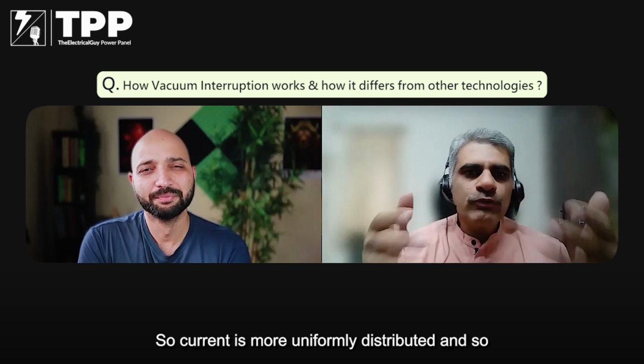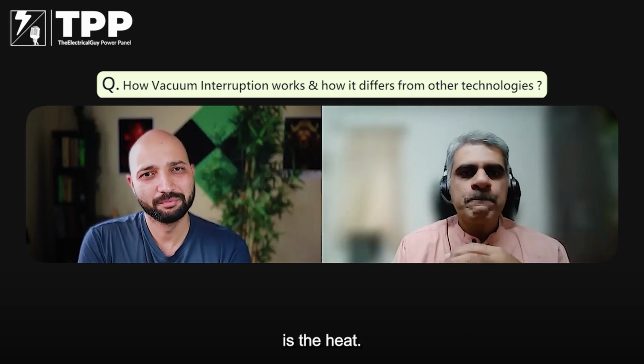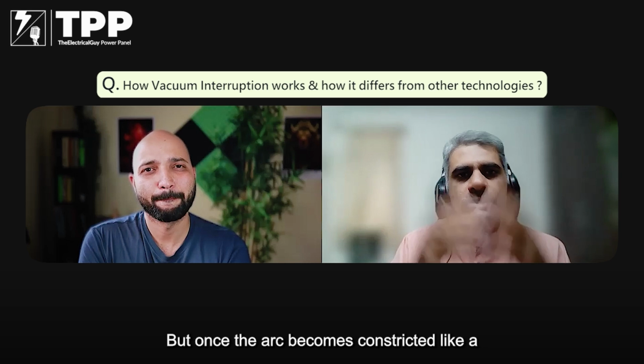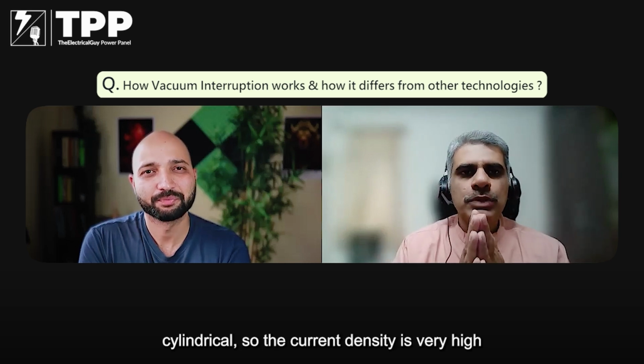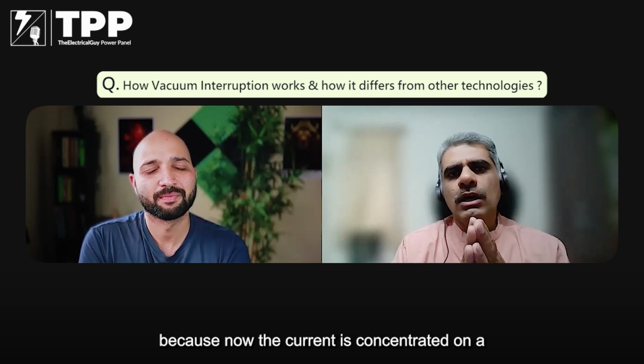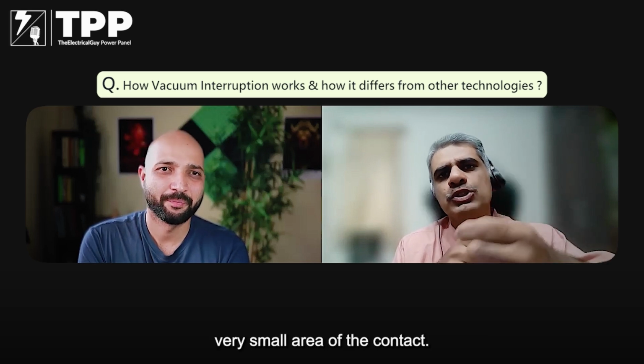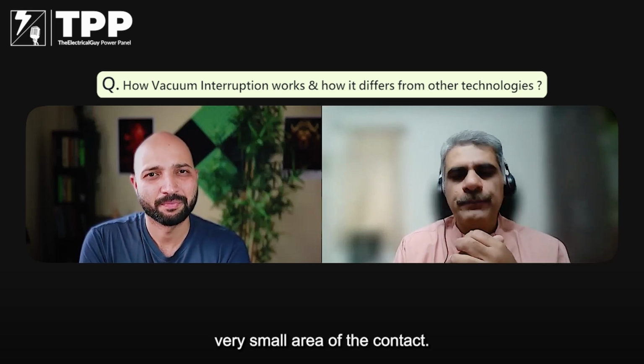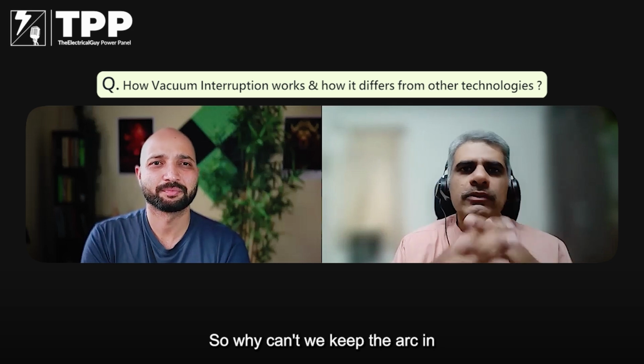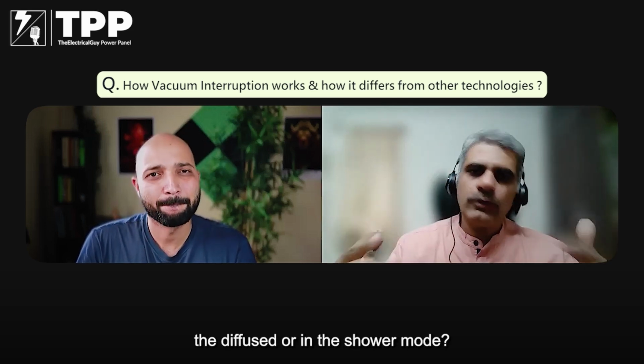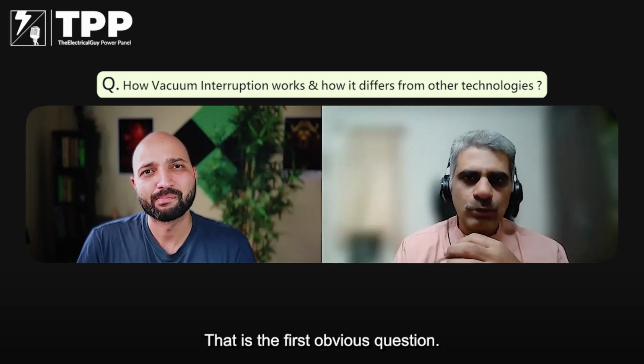So current is more uniformly distributed, and so is the heat. But once the arc becomes constricted, like a cylinder, the current density is very high because the current is concentrated on a very small area of the contact. So why can't we keep the arc in the diffused or in the shower mode? That will be the first obvious question.